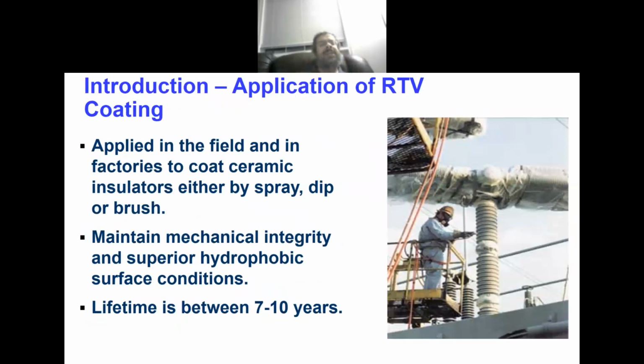Then came the solution of RTV coating. The RTV coating is basically a room temperature vulcanized coating made from silicone rubber, the same material used for the non-ceramic insulators we started with. So you spray the insulators and gain the advantage of a low surface energy, or hydrophobic surface.